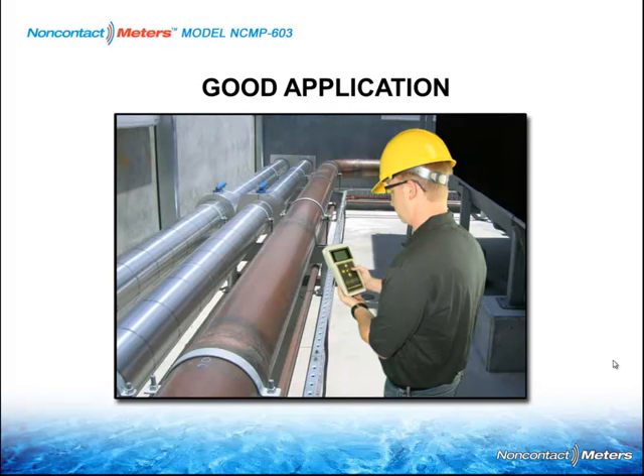Even on a perfect application, where we have lots of straight run of pipe, you may have some applications that have some serious insulation on the pipe. You will have to remove insulation from the pipe itself. So this particular case has a metal shielding on the outside of the insulation. So the maintenance people may have to actually prep the pipe for you. You may not have the tools in your toolbox to take this off the pipe, and they want to put it back on pretty. If you have the foam insulation, of course, it's a lot easier, but take into account what you require to actually get to the pipe itself. You may require scaffolding and ladders, or you may have to remove insulation off of piping to get your good application.